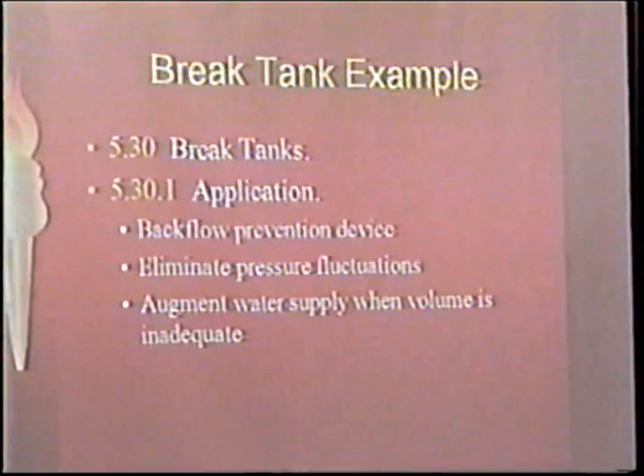So that's why I'm saying, I think an underground storage tank or an above-ground storage tank makes sense in a well situation because it has the 8-hour refill requirement. But with this break tank, when I saw that 110% flow requirement on the refill, that really is going to limit its applications. If you have a city water supply, I don't think that's going to be a problem.